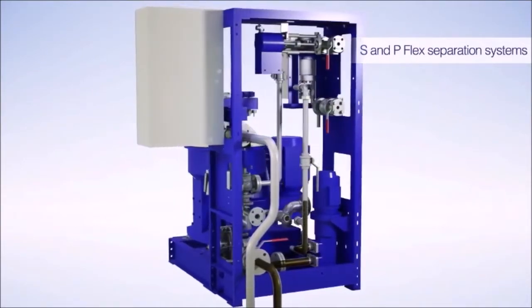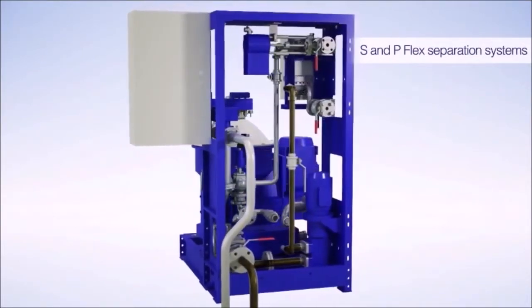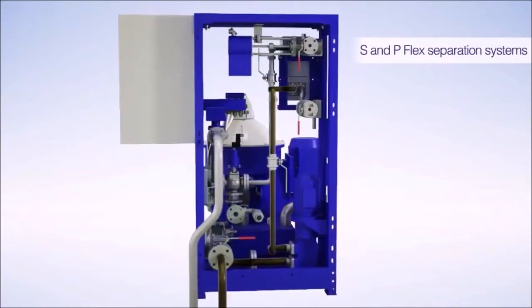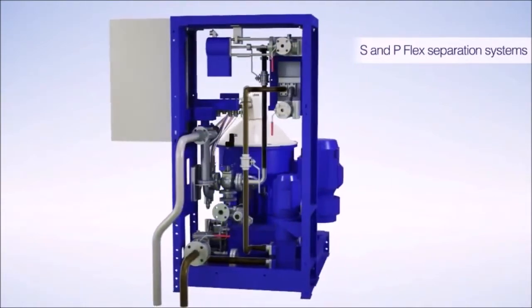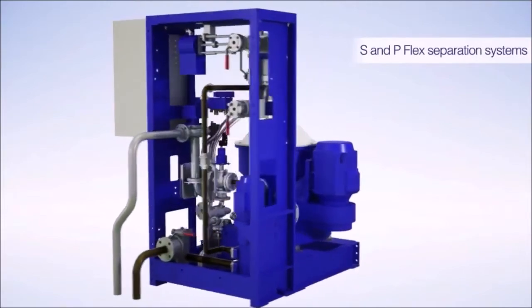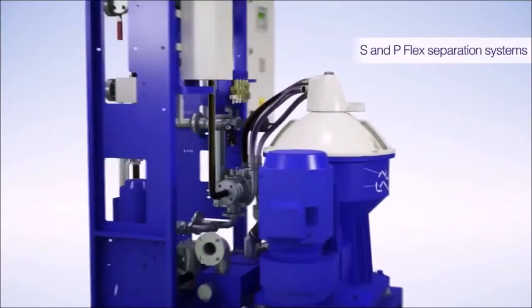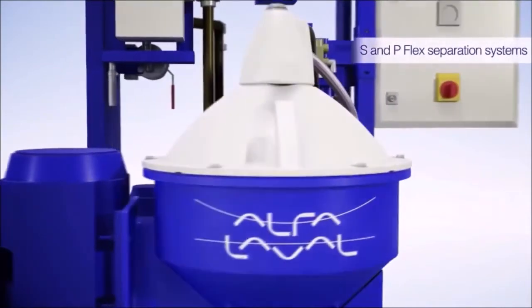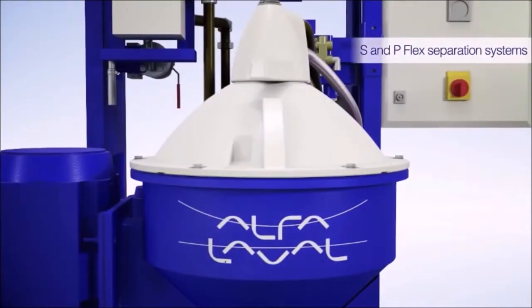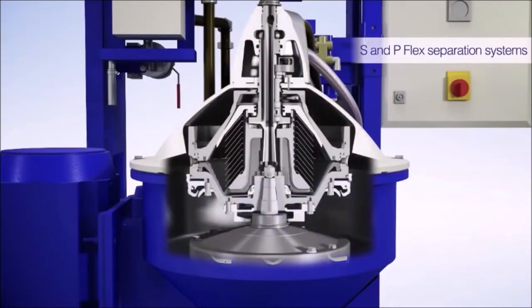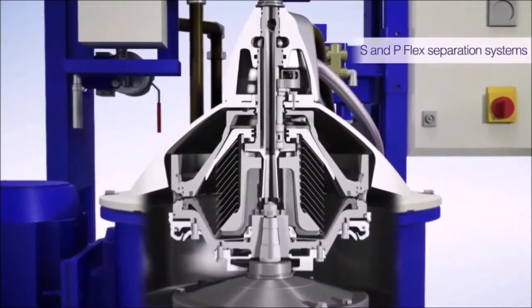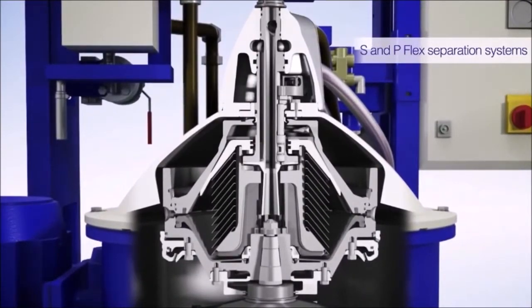How does a centrifuge work? A centrifuge consists of an electric motor driving a vertical shaft, on top of which is mounted the bowl assembly. Centrifuges work by rapidly spinning a bowl containing the liquid, producing the centrifugal force required to produce separation. When a bowl containing impure fluid is rotated, centrifugal force will throw any item with density greater than the fuel oil density, such as solids and free water, to the periphery of the bowl.